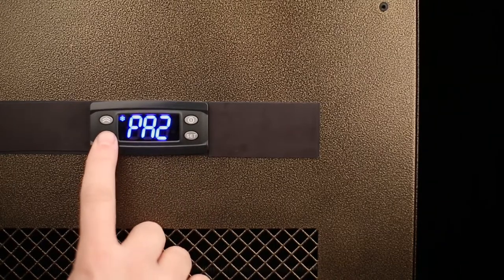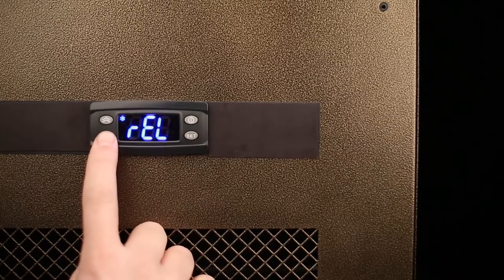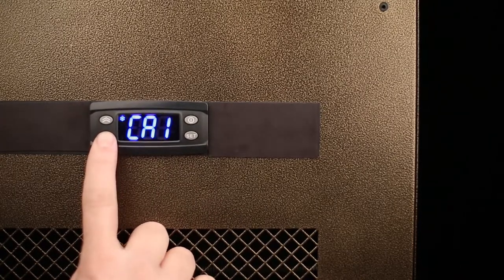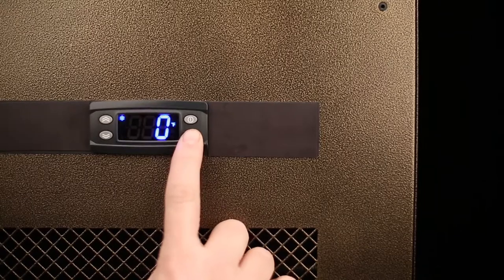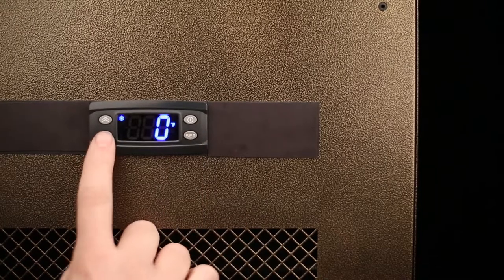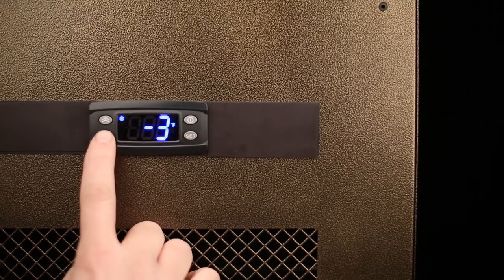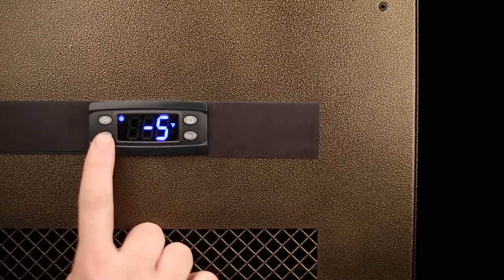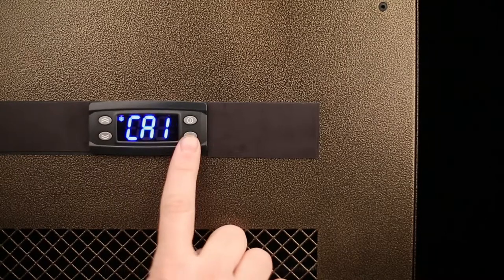Once LOC is displayed, scroll down to the CA1 parameter and press the set button. Decrease this value and press the set button to set the temperature differential. Modifying this value will change the air probe reading.